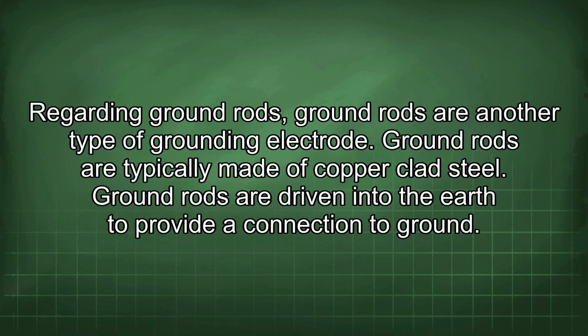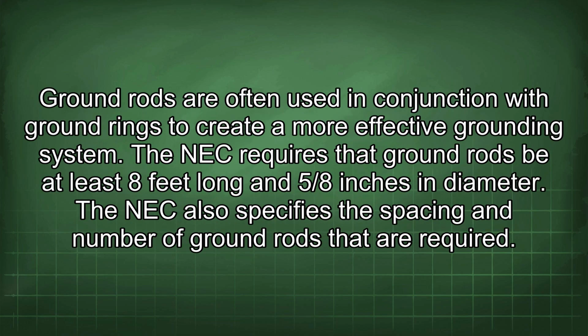Regarding ground rods, they are another type of grounding electrode. Ground rods are typically made of copper-clad steel. Ground rods are driven into the earth to provide a connection to ground. Ground rods are often used in conjunction with ground rings to create a more effective grounding system. The NEC requires that ground rods be at least 8 feet long and 5/8 inches in diameter. The NEC also specifies the spacing and number of ground rods that are required.